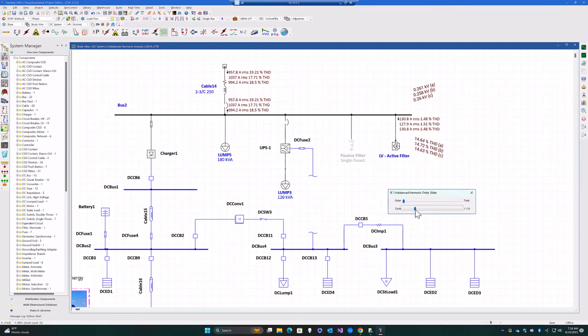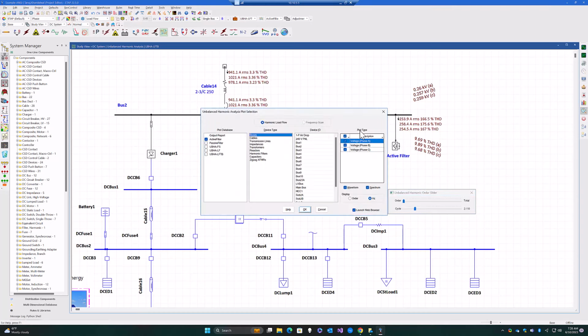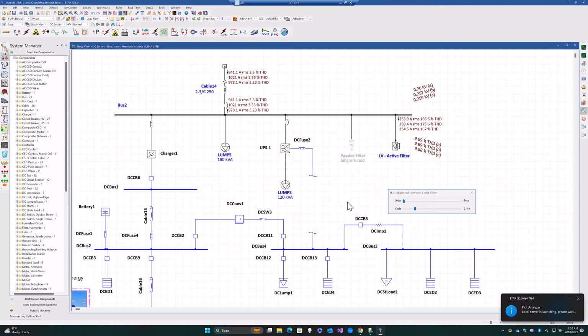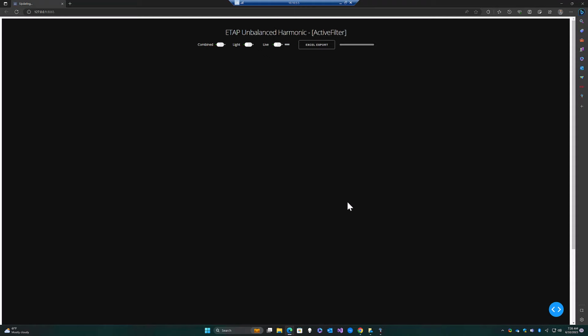But as the cycle moves on, you can see that the filter is able to achieve within 10 cycles a very, very good amount of compensation. In fact, the compensation happens within 2 cycles itself, and we've brought it down significantly to 3.3. The combination will give you a better indication of what is actually happening in the system. So let's just take bus 1, and we can also compare with bus 2 to see what's happening, and we can compare with the main bus as well, which is the point of common coupling. So let's go ahead and see what these charts look like for 3 different buses, not comparing with the passive filter, just the active filter case by itself.